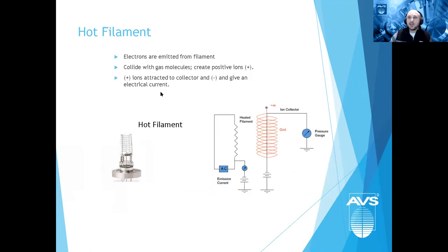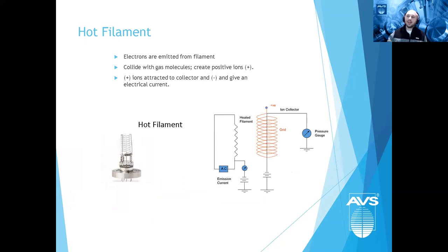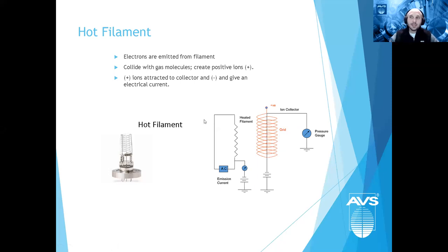The hot filament ion gauge has a heated filament — tungsten, yttria-coated iridium, or thoria-coated iridium — through which current is sent to emit electrons. These electrons bombard neutral gases, ionizing the gas particles. The ions are collected on the collector (thin wire), producing a current that indicates pressure. For cold cathode gauges, there's no filament — instead, internal magnets and an internal plasma (ignited by an ignition aid) are used, similar conceptually to a sputtering process with electron bombardment.